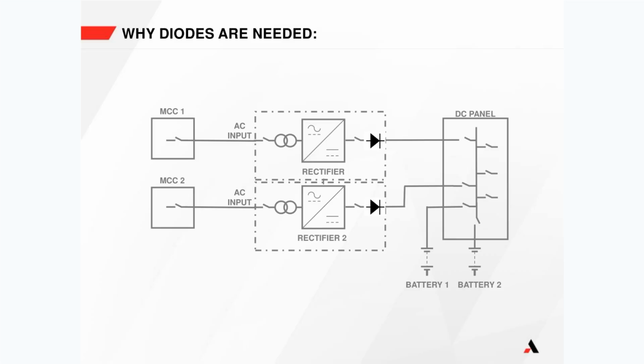Ideally, this one should be 135 volts and this one should be 135 volts too, and if it's been set up and calibrated correctly, it should be. But even a 0.5 volt difference between the two systems could lead to the problem I mentioned on the previous slide. Adding these diodes prevents that from happening, so it's a good thing.